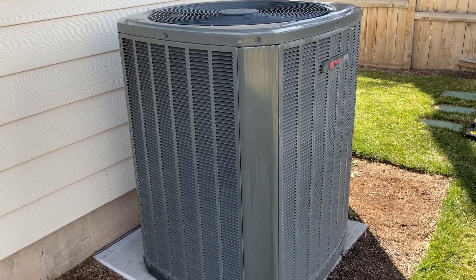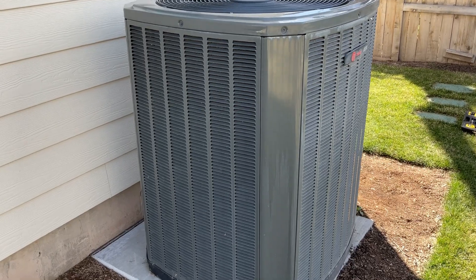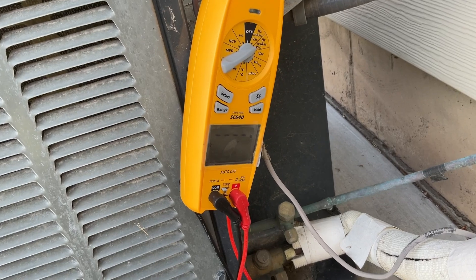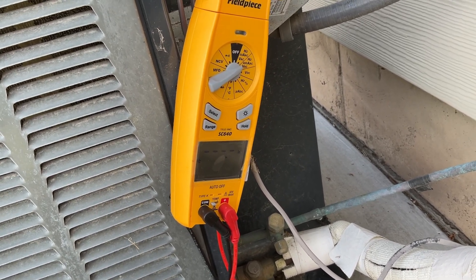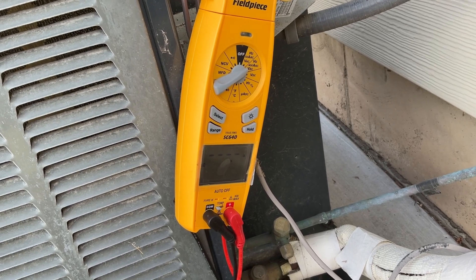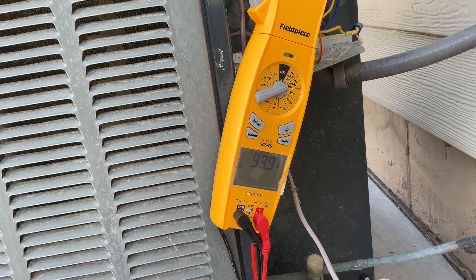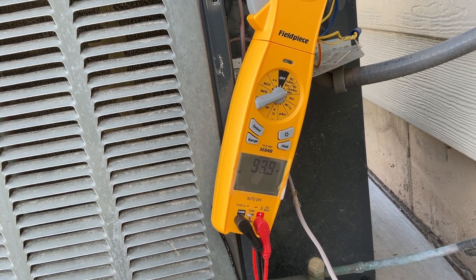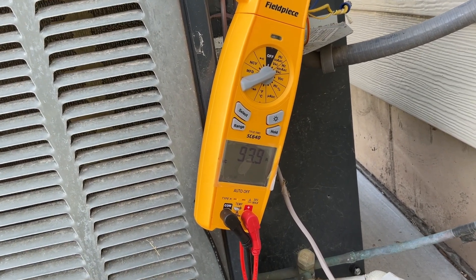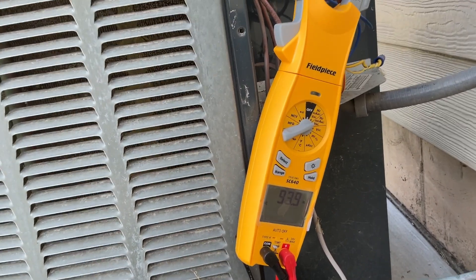Today we're going to install a Micro Air EasyStart for this Trane air conditioner. I'll trigger the air conditioner to come on and we'll see what the inrush is on this unit without the EasyStart. The inrush recorded at 93.9 amps — that's a lot.